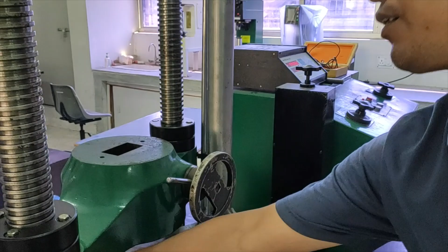And these are for 3-point bending - one pair of fixtures is available for that. One mandrel will be put in the center of this lower crosshead, then we can perform the 3-point bend testing.